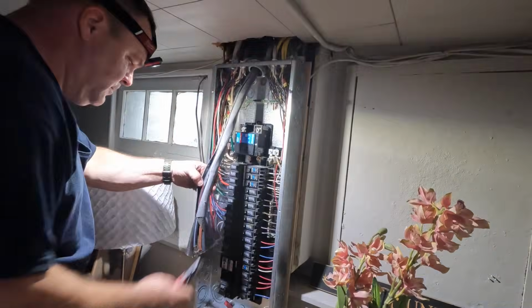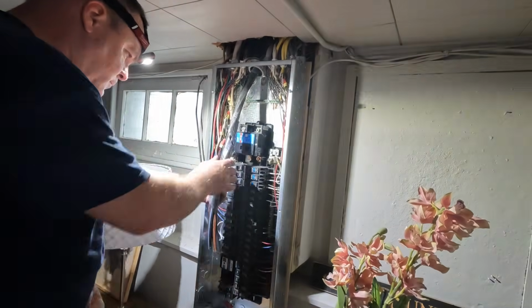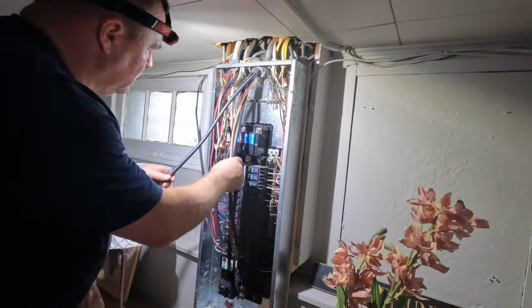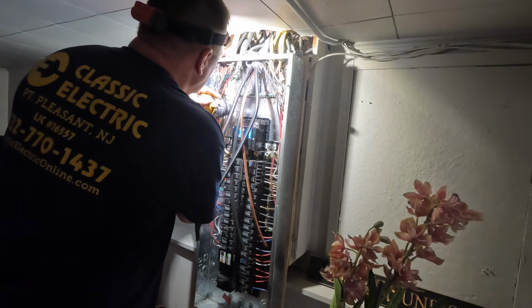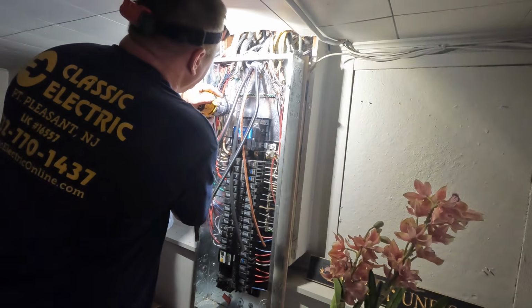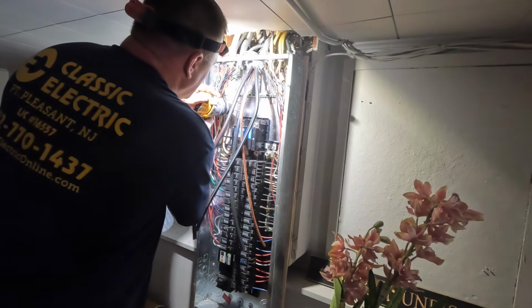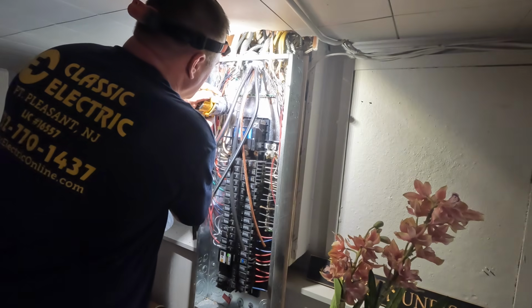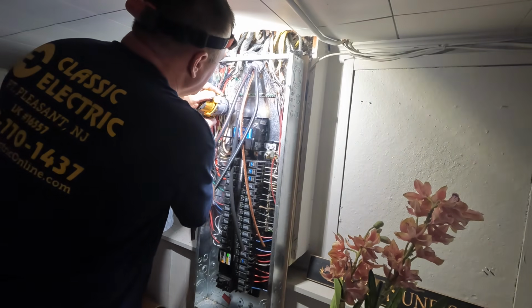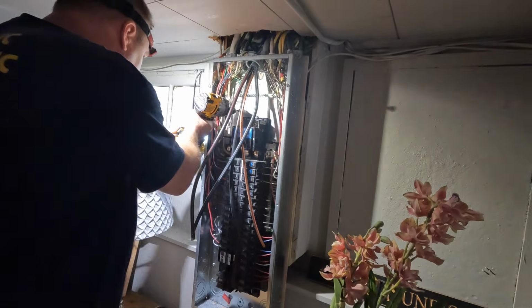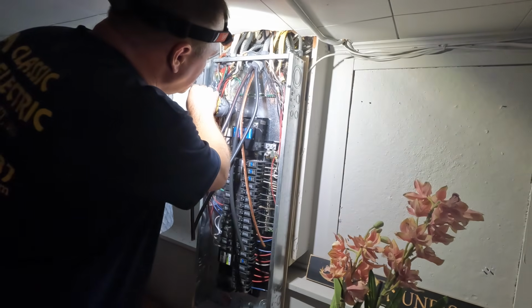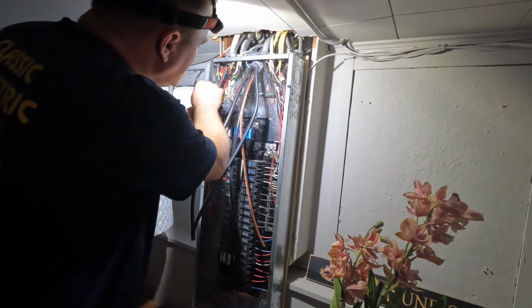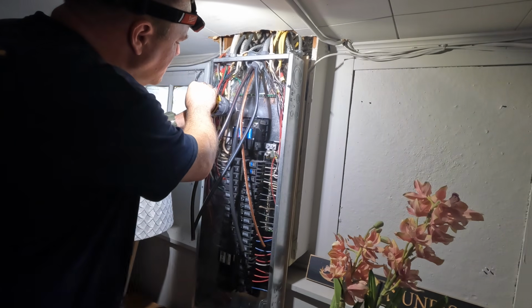So the next step is to terminate these new conductors, and the first thing I'm going to do is terminate the equipment grounding conductor. And there's only a few ways to do this listed in Article 250.8. Here I am drilling a hole and then using 1/4-20 threads to attach a 1/4-20 bolt and attach a lug to mechanically connect my equipment grounding conductor.